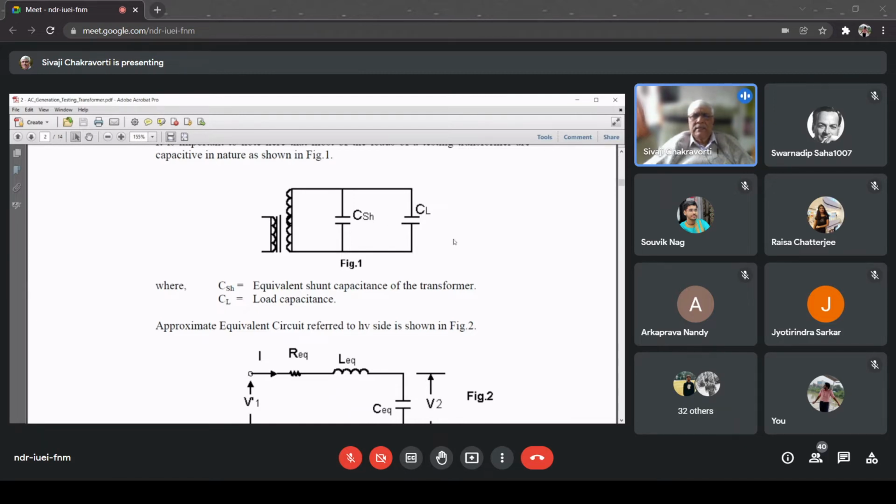But the point is, see, this we have to know technically. That's the difference between a technician and an engineer. And you are all high voltage engineers, or rather studying high voltage at Jadavpur University. So you should be aware of this sort of technicalities. So therefore, we should never perform test anywhere, wherever you will be working later on. Please don't test by multiplying by the turns ratio. You have to always actually measure the voltage across the test object by placing a suitable voltmeter which can measure this high voltage.